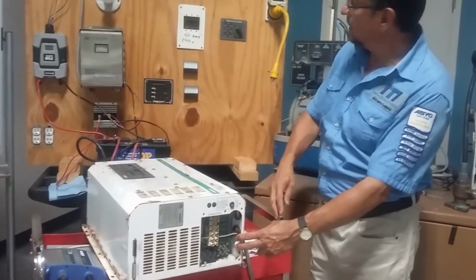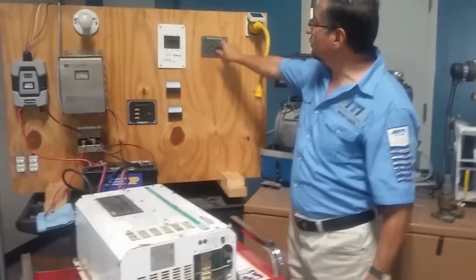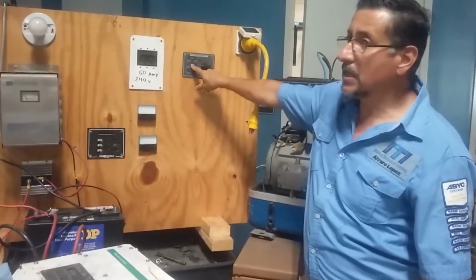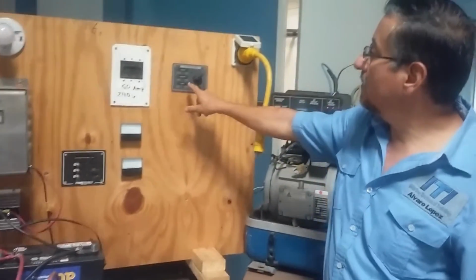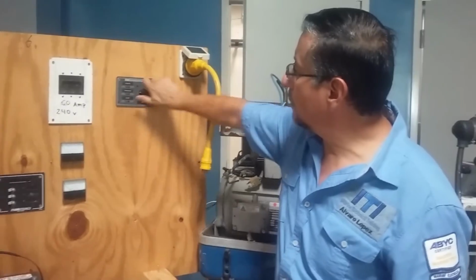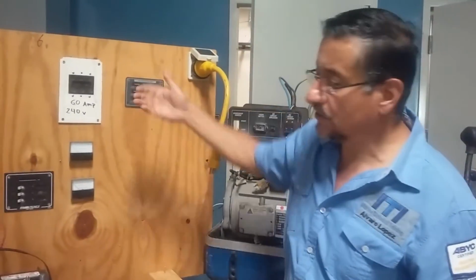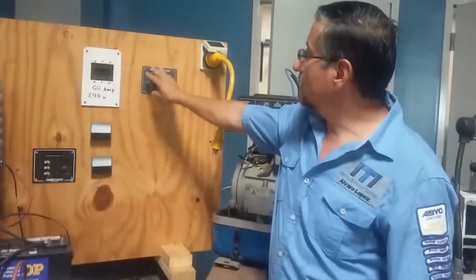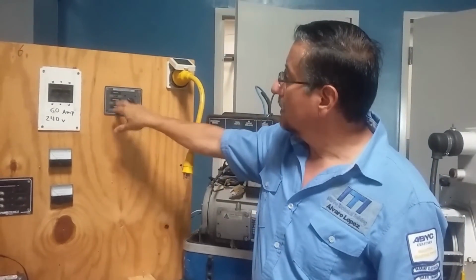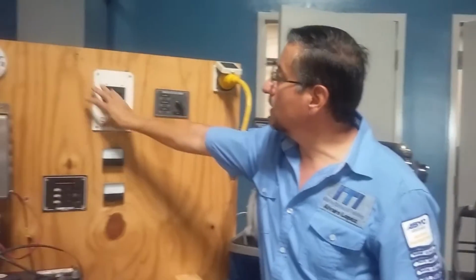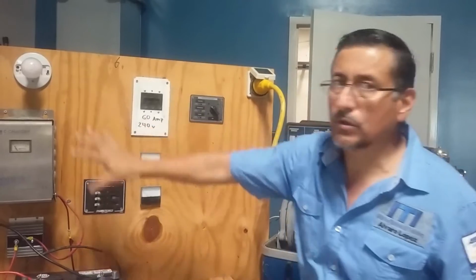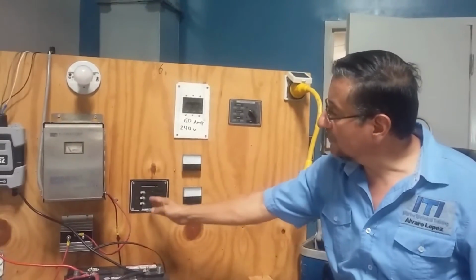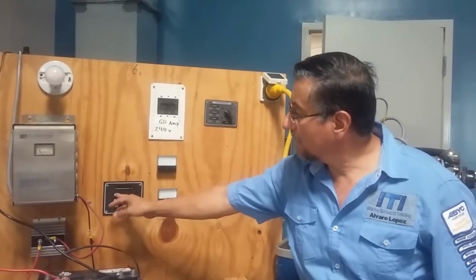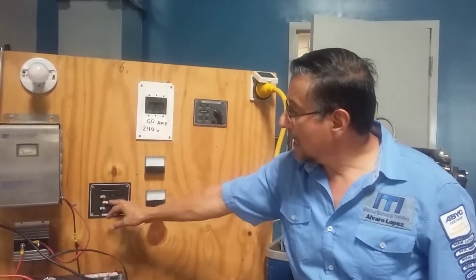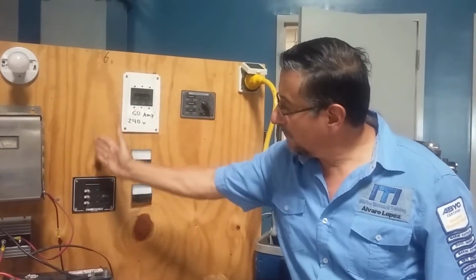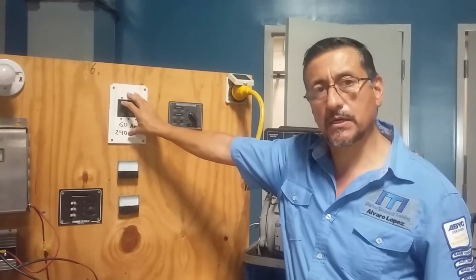The output AC power enters into the switch selector. In the switch selector, you can select inverter or generator or shore power, depending if the power is coming from the shore, or from the generator, or from the inverter. This is the switch selector. After the switch selector, the output enters into the main breaker. This is the main breaker of the boat. And after the main breaker, you have the single breakers or specific breakers: breaker for battery chargers, for lights, for appliances, different breakers.